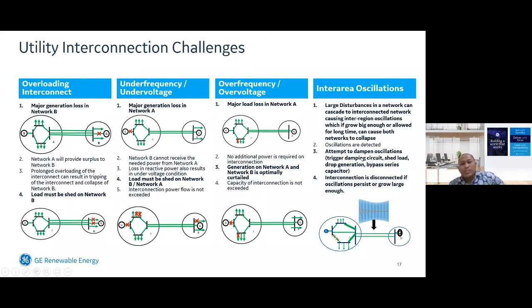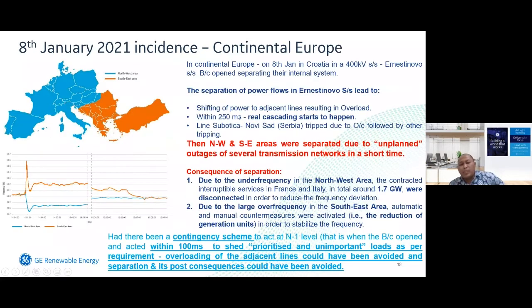So this is an example, or experience, that we got from continental Europe, where a separation of power flow happened in the Ernestinovo substation, which led to the shifting of power to the adjacent line, resulting in overload. Then within 250 milliseconds, real cascading started to happen. The line Subotica to Novi Sad in Serbia tripped due to overcurrent, followed by other trippings.